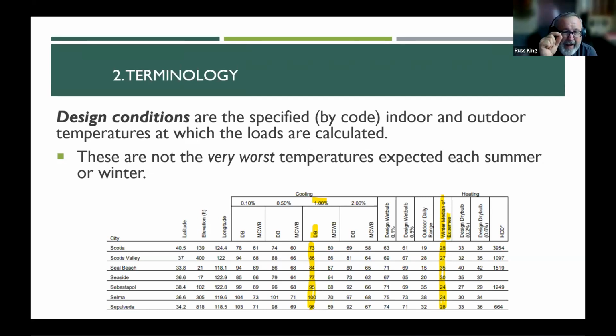But 1% is not that much. 1% is a very, very tiny amount of time. And that's not days, that's hours, okay? It's not 1% of the days it's going to exceed that, it's 1% of the hours. So if you look at a temperature graph, it gets very hot during the day, it peaks, and it comes back down. 1% of the time, that peak is going to be above that number, and it's going to be for a very short period of time. And you can deal with that. There's things you can do to make your house deal with that, okay?